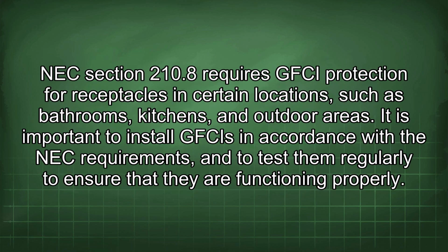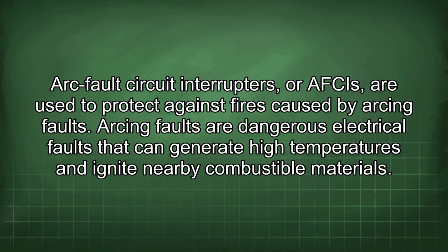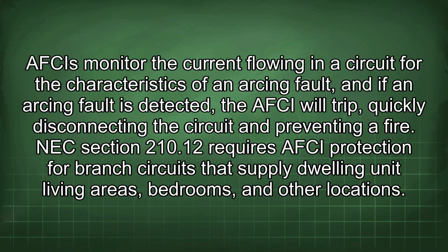NEC Section 210.8 requires GFCI protection for receptacles in certain locations, such as bathrooms, kitchens, and outdoor areas. It is important to install GFCIs in accordance with the NEC requirements and to test them regularly to ensure that they are functioning properly. Arc fault circuit interrupters, or AFCIs, are used to protect against fires caused by arcing faults. Arcing faults are dangerous electrical faults that can generate high temperatures and ignite nearby combustible materials. AFCIs monitor the current flowing in a circuit for the characteristics of an arcing fault, and if an arcing fault is detected, the AFCI will trip, quickly disconnecting the circuit and preventing a fire.